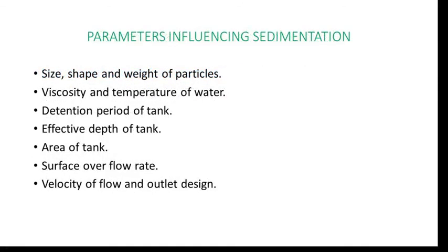These are the various parameters that influence the sedimentation process. Size, shape, and weight of the particle: if the particle has a very fine size, it does not easily undergo the settling process, so the size should be larger so that it can easily settle. Then the viscosity and temperature of water, detention period of the tank, effective depth of the tank, area of the tank, surface water overflow rate, and velocity of flow and outlet design. So these are the various parameters that influence the sedimentation process.